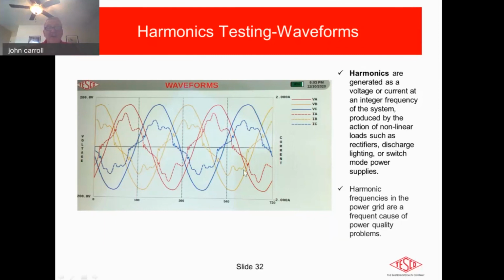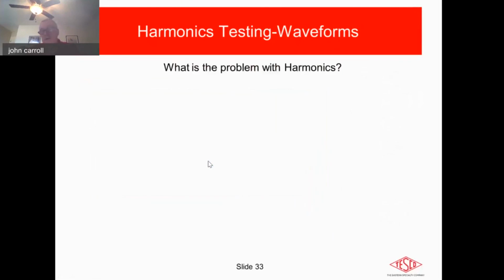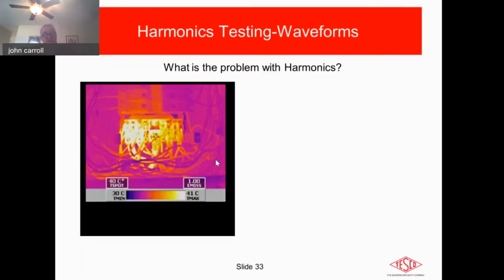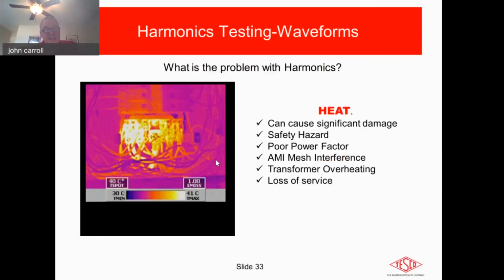All of this, the important thing of all of this is, how does it affect us? So the question I'm going to finish with, to a certain extent, on this is, what's the problem with harmonics? Well, the number one problem with harmonics is illustrated by that picture right there. And you may have already figured out that the real big problem with this is heat. And these types of harmonics don't propagate down a cable in the center core of the cable. It's not designed that way. So they have what they call skin effect. So it kind of spins around the cable and creates a hot cable.